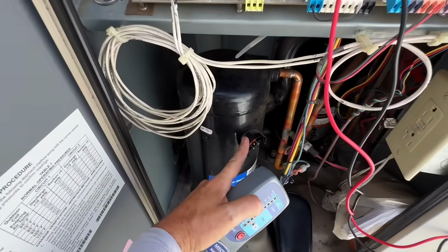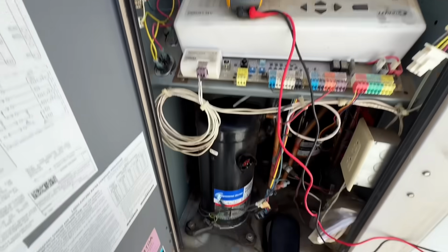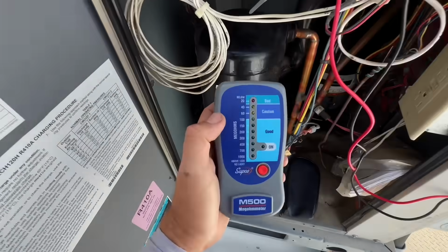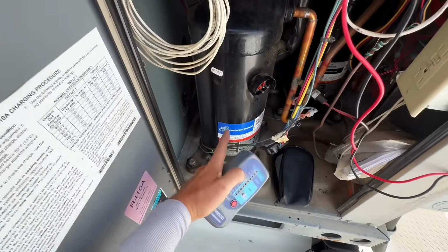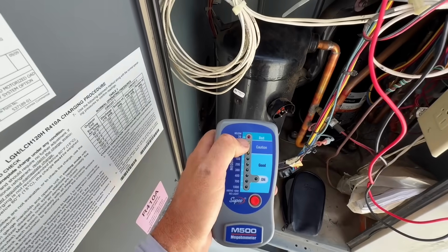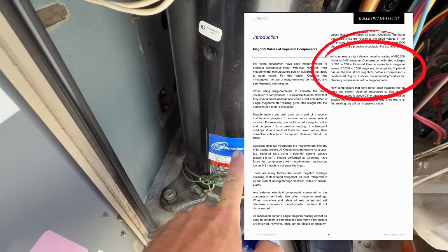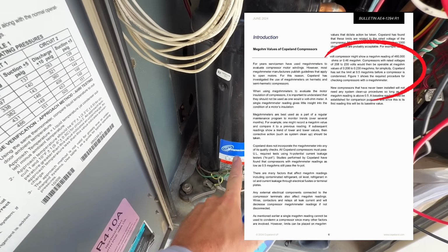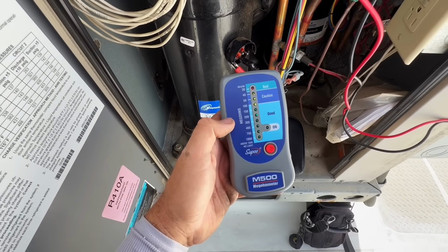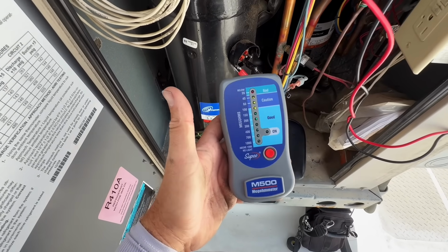So it's most likely that the insulation is worn out and we do have a connection to ground, but we were not able to see it on here, which is why I'm using this as a tool to confirm my theory instead of using it as the sole tool to diagnose. Because if you read the literature on the Copeland compressors, this only reads to 20 megohms, and some of these compressors can still be good at like 0.5 to 1 megohm. That being said, I would recommend investing in a high quality megohm meter if you have the funds for it. Otherwise, use this as an added diagnostic tool.